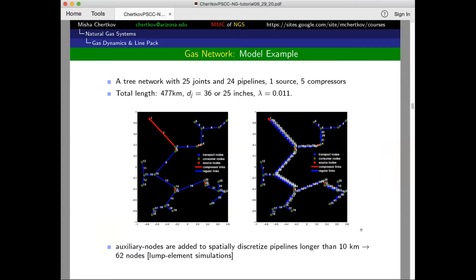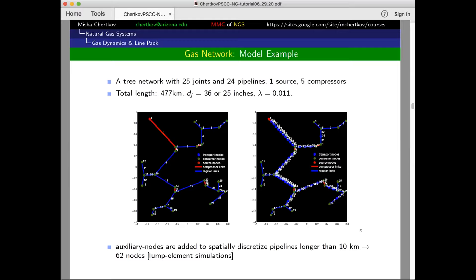Gas networks are often trees. That's a typical model you start with. An advantage of the lump-element method is that you can add nodes adaptively as needed — especially when there are significant changes along a particular line, you put more nodes. You see here typical parameters: a 500-kilometer system, still tree-like, and the discretization that would be important is on a scale of 10 kilometers.